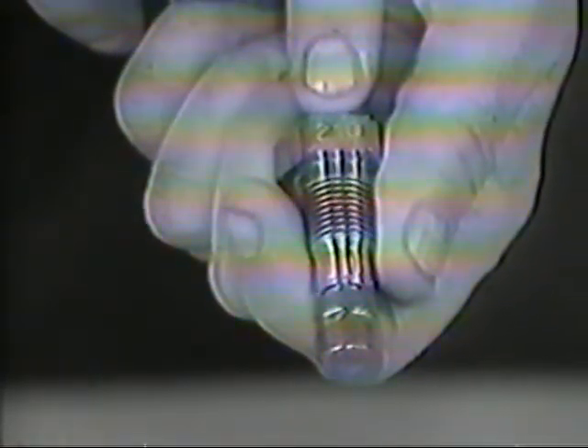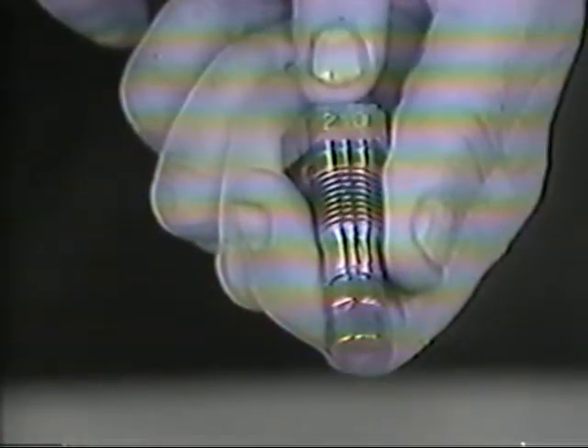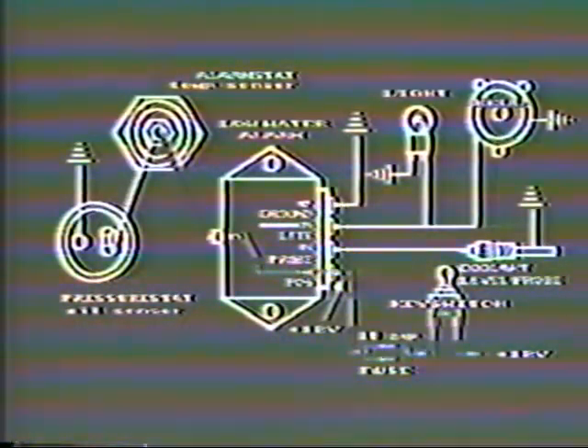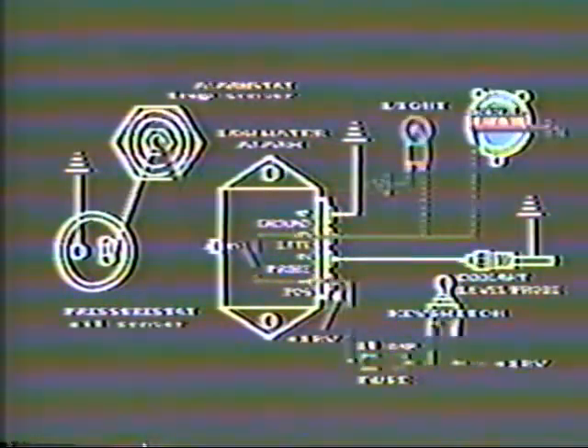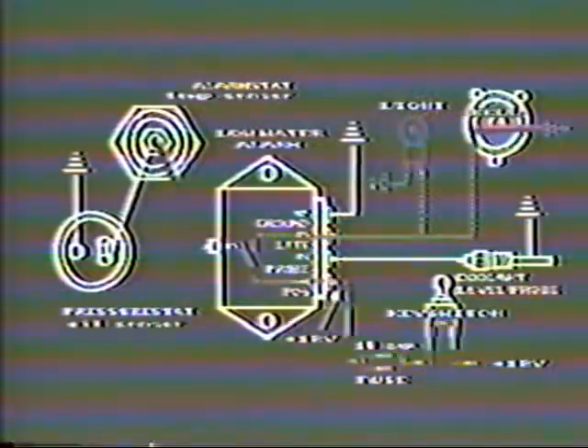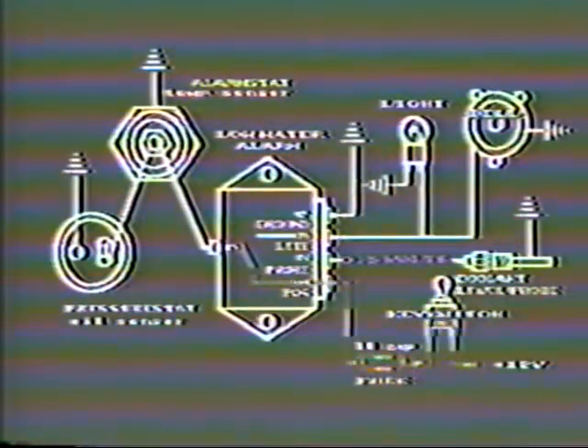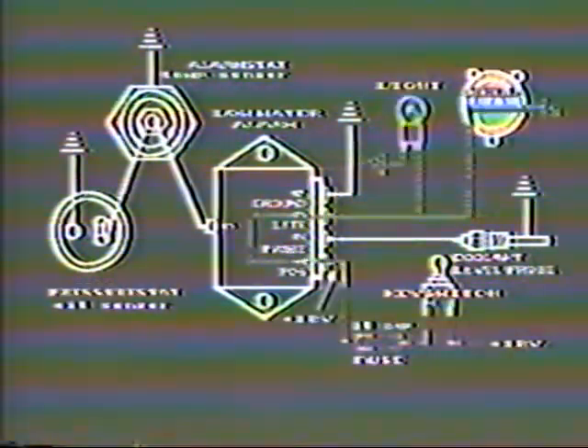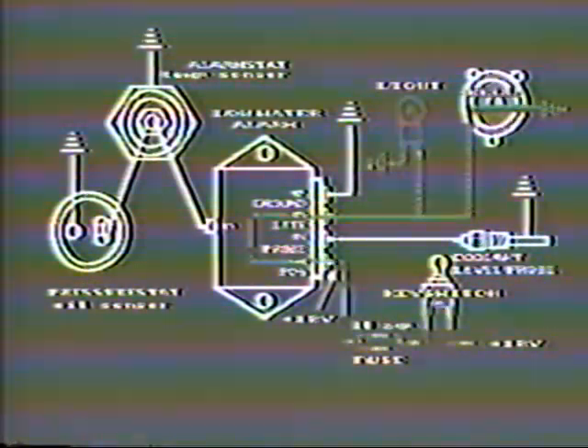A similar process takes place for a high temperature alarm. The alarm stat in this system is normally open and is set at 210 degrees. If engine temperature reaches 210 degrees, the normally open alarm stat switch closes and connects its terminal to ground. The ground reaches module terminal number 5 through the wire and the module switch closes. Voltage reaches the light and bell and a high temperature alarm is given. A low coolant alarm begins when coolant drops away from the coolant level probe. As coolant drops away, the ground at the probe and at module terminal 2 is lost. As the ground is lost, the voltage at terminal 2 rises. When terminal 2 voltage reaches 3.5, the module triggers the low water alarm, closing the internal switch and giving voltage to the light and bell.